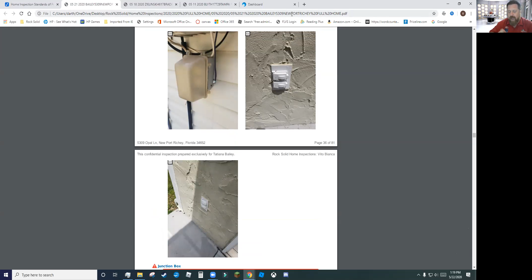So even though it's $1,000 to replace the panel, it's worth doing because you'll save that money from premiums and possible damage the companies won't leave you exposed to. Now let me stress, we're inspectors. We have no control over what's insurable or not. What we do have is a framework of reference to call out that these panels have been recalled, these panels might have trouble getting insured, these panels tend to get more of a risk of a fire hazard over time, and we call that out.